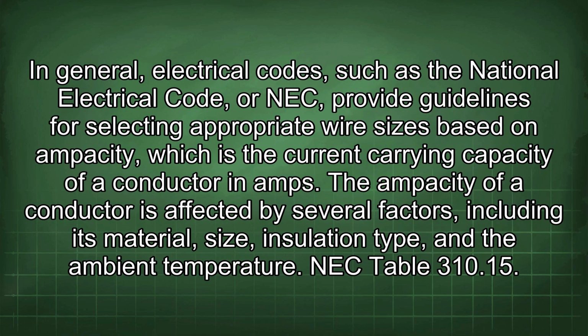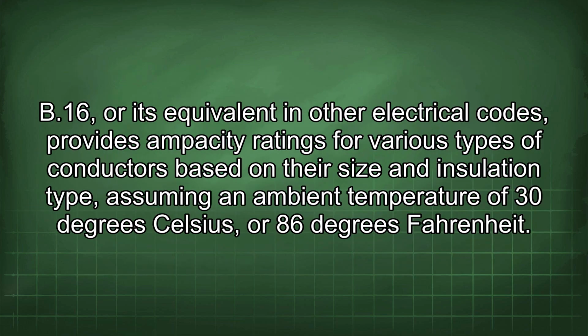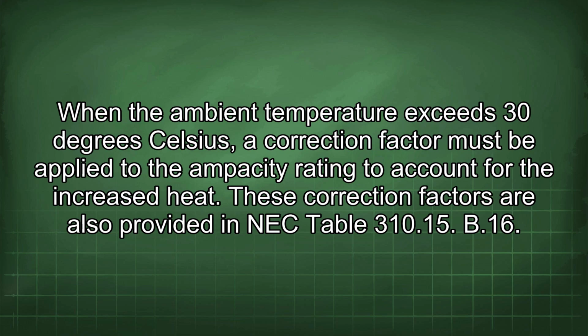In general, electrical codes such as the National Electrical Code, or NEC, provide guidelines for selecting appropriate wire sizes based on ampacity, which is the current carrying capacity of a conductor in amps. The ampacity of a conductor is affected by several factors, including its material, size, insulation type, and the ambient temperature. NEC Table 310.15(B)(16), or its equivalent in other electrical codes, provides ampacity ratings for various types of conductors based on their size and insulation type, assuming an ambient temperature of 30 degrees Celsius or 86 degrees Fahrenheit. When the ambient temperature exceeds 30 degrees Celsius, a correction factor must be applied to the ampacity rating to account for the increased heat. These correction factors are also provided in NEC Table 310.15(B)(16).